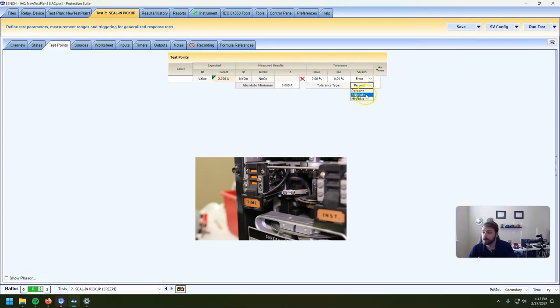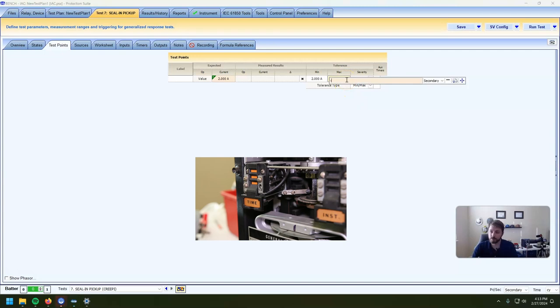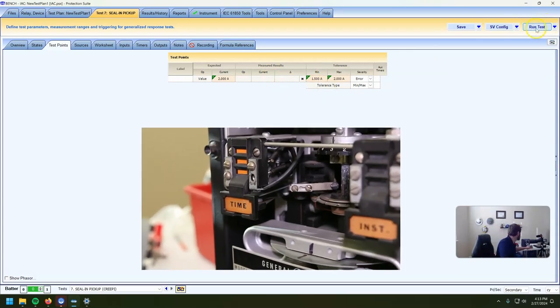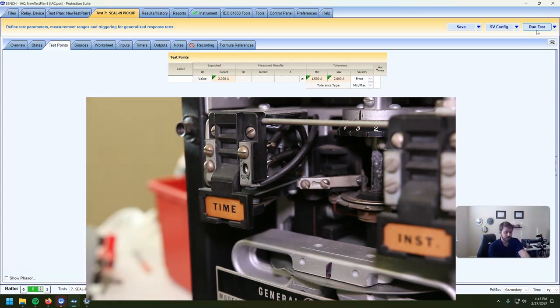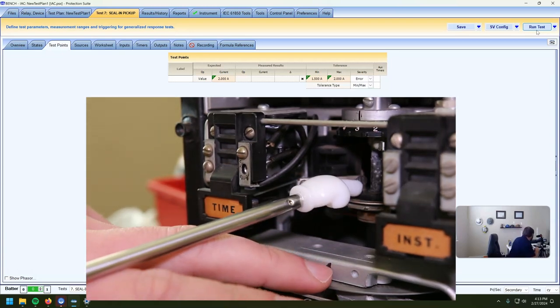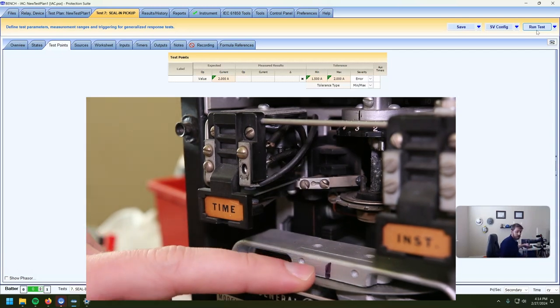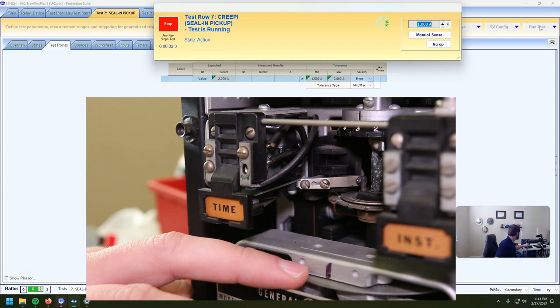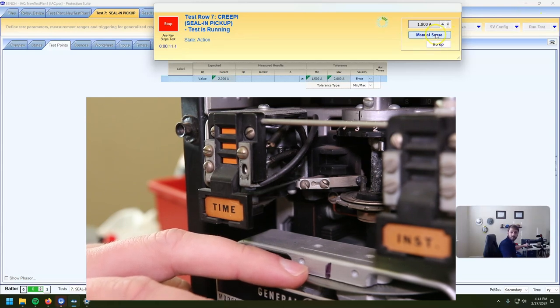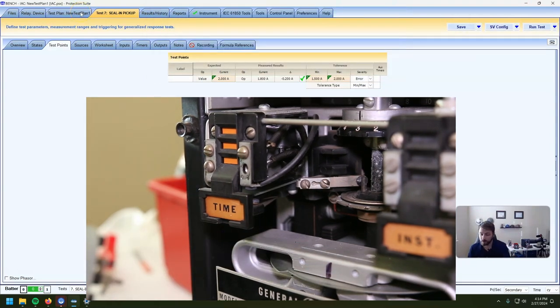I didn't put a tolerance in here — for these I always put in min/max. Our max is the max expected value and our minimum is 75%. Let's try that again. We have to hold that contact all the way operated, all the way closed, and then start our test current. We increase until it picks up. And there we go — that is that test.